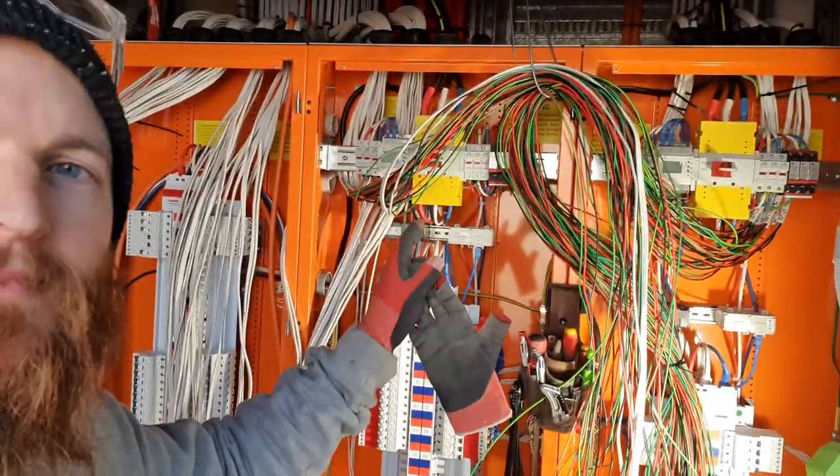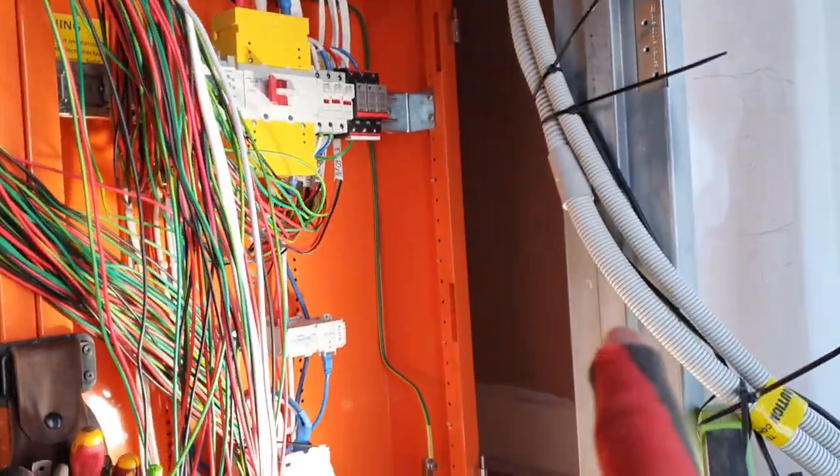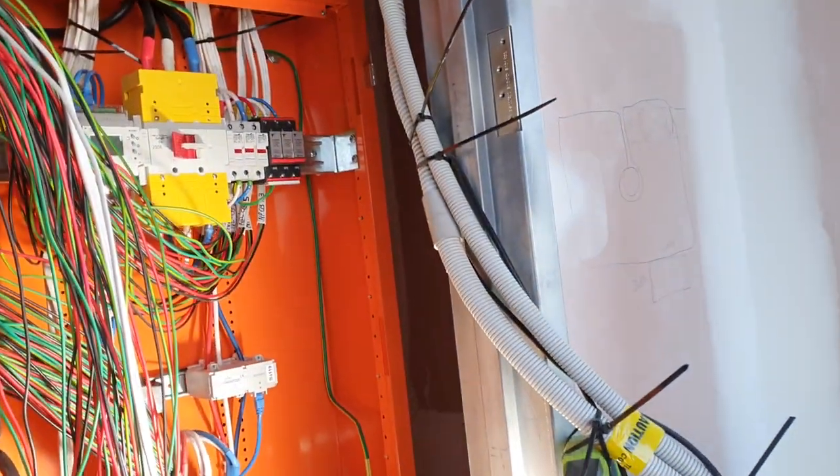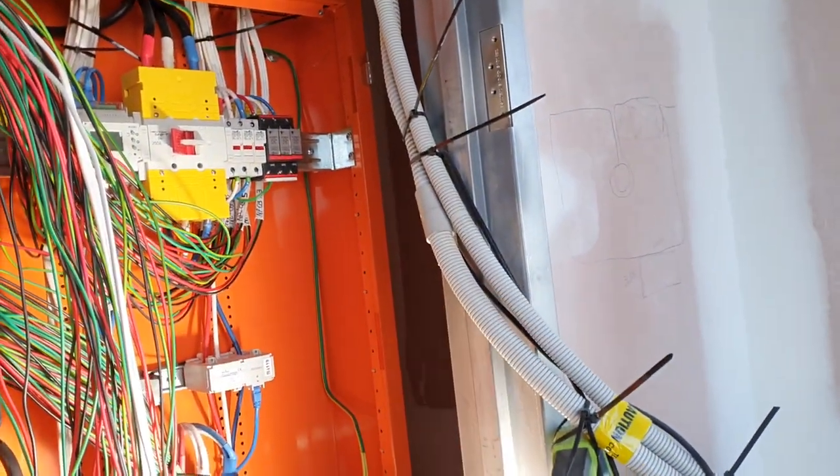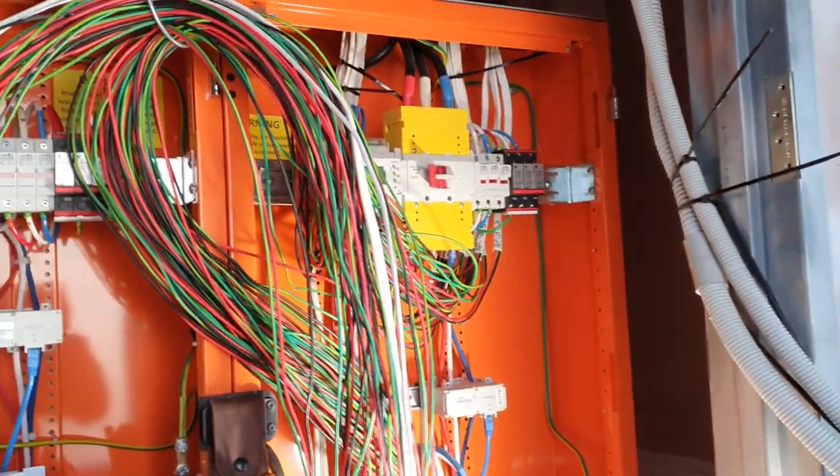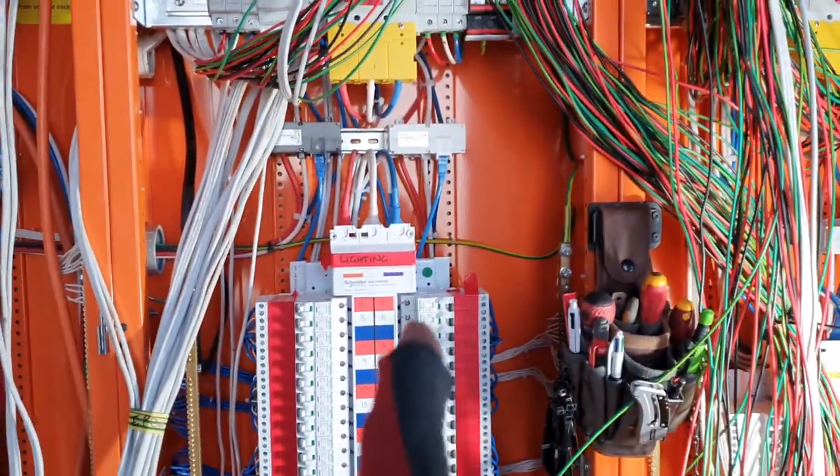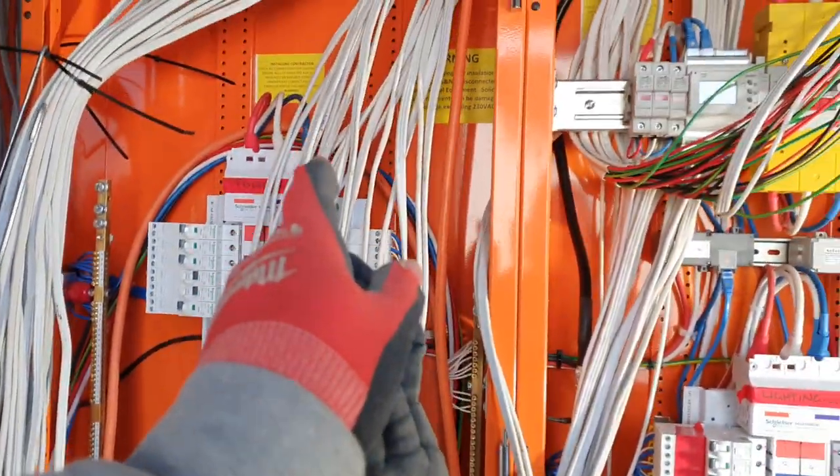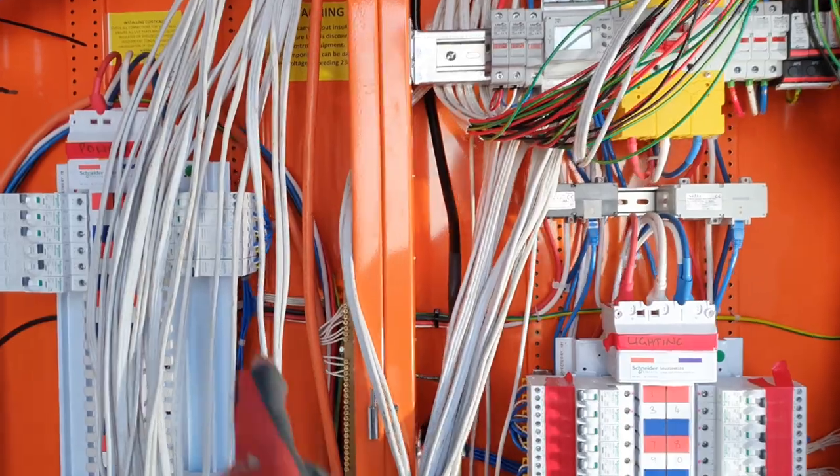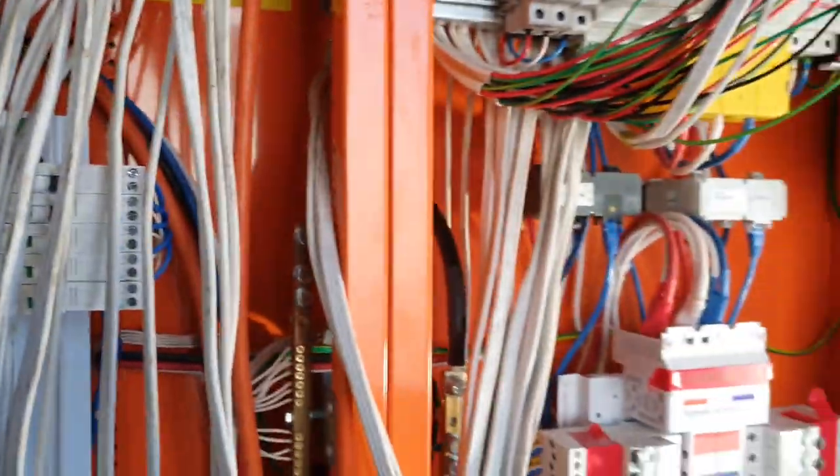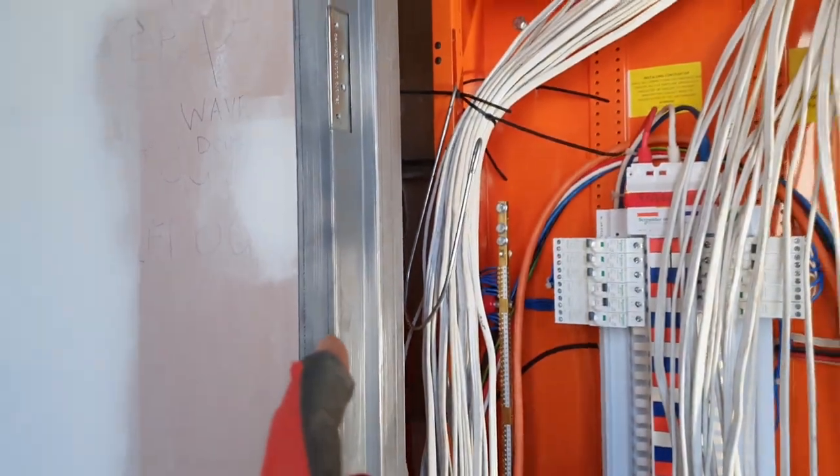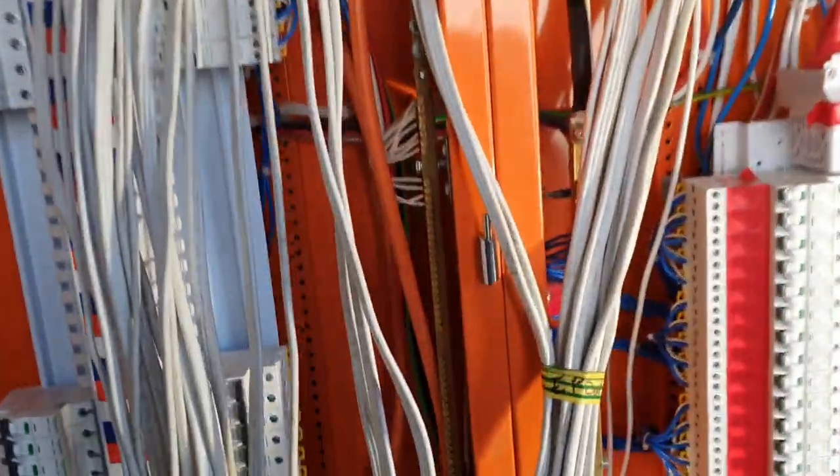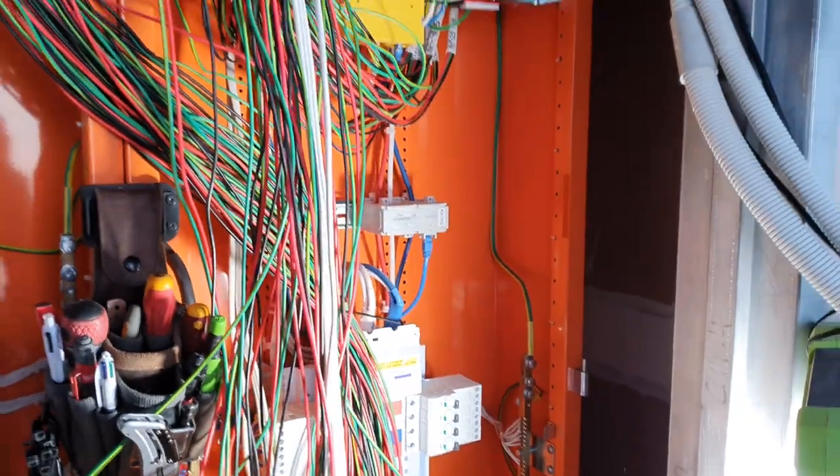I've got the boards on now. Don't cry me for it, but the door, they're too far out. I'm trying to get the builder to consider putting a bigger door. I'm not sure he's going to do it. This isn't actually to code, but there's not a whole lot I can do about it. I didn't realize this was a double panel. This is essentially like this board and this board here are the same board electrically. So the cabling goes from the main switch there across through there and up to the top of the chassis there. I didn't realize this at the time and I would have got them to order a bigger door. But these doors are very expensive and now I'm in a bit of a pickle because I'm not following the rules to the letter.